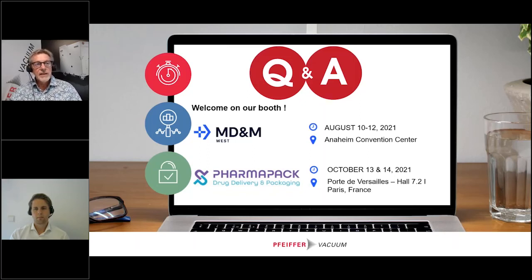This is something you have to consider, and it makes the helium test quite difficult to set up in production. But it's possible. Some companies are using helium tests to perform IPC tests. That's for me.